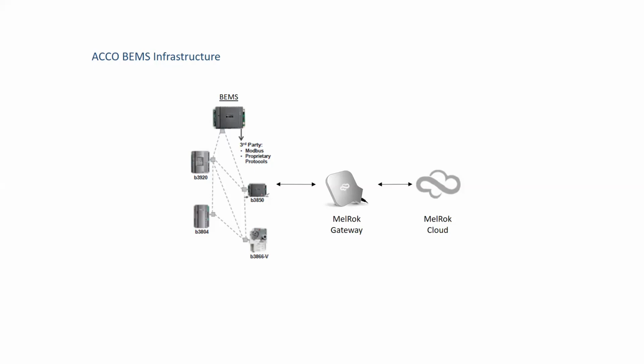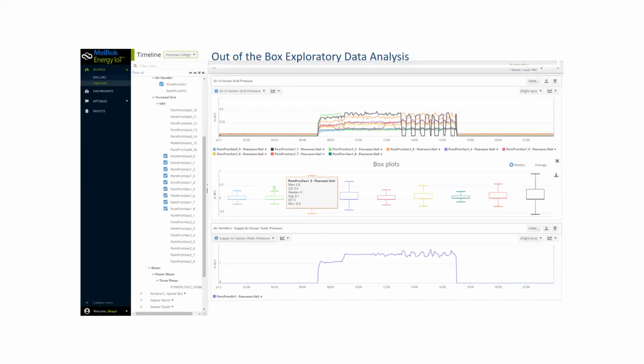What you end up with is an out-of-the-box system where you can use a lot of data science tools and do exploratory data analysis. In this example, I'm showing an air handler and its associated VAVs, looking at velocity pressure and the air handler supply static pressure, using out-of-the-box statistical tools like box plots. Box plots are phenomenal tools for looking at a number of VAVs, especially when it comes to velocity pressure.